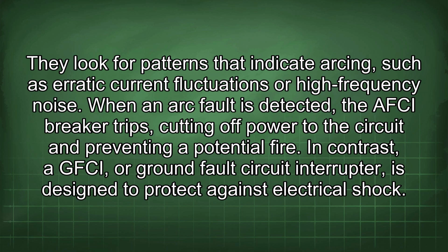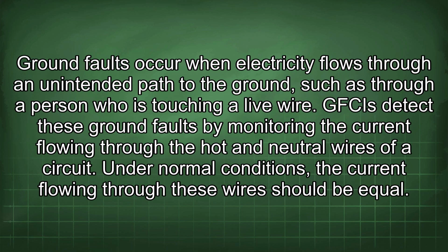When an arc fault is detected, the AFCI breaker trips, cutting off power to the circuit and preventing a potential fire. In contrast, a GFCI, or ground fault circuit interrupter, is designed to protect against electrical shock. Ground faults occur when electricity flows through an unintended path to the ground, such as through a person who is touching a live wire. GFCIs detect these ground faults by monitoring the current flowing through the hot and neutral wires of a circuit.